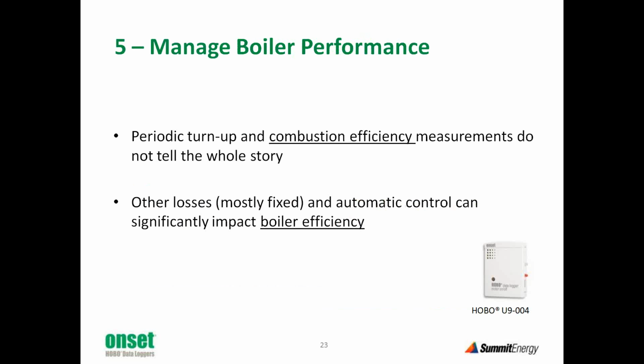We're ready to move on to number 5, manage boiler performance. Now, when you ask about boiler performance, many of my clients show me a strip of paper that almost looks like a cash register receipt that says they're running 83% efficient and they have a tune-up every year. Well, but that's not the whole story. That piece of paper that comes from your tune-up guy shows the combustion efficiency. And it's pretty accurate for the combustion efficiency, but there are other losses, and they're mostly fixed.